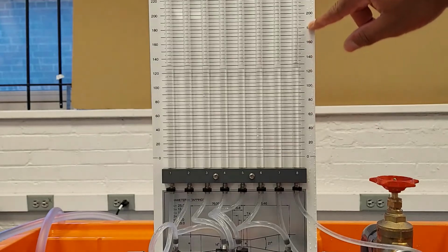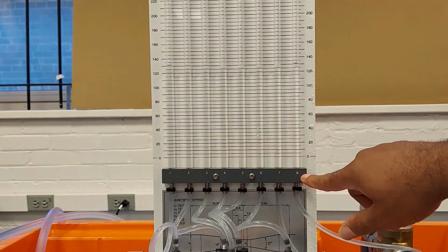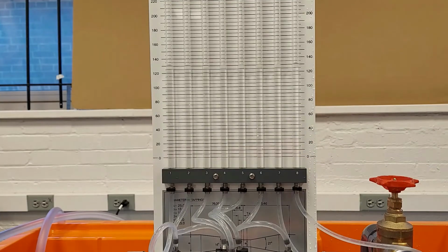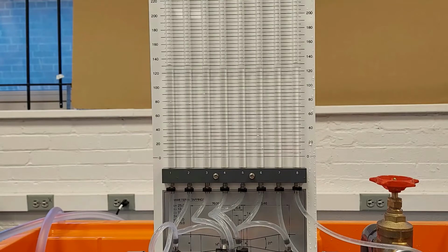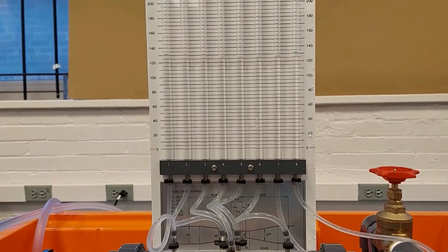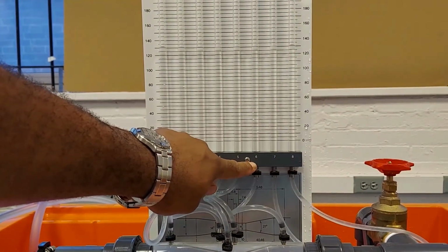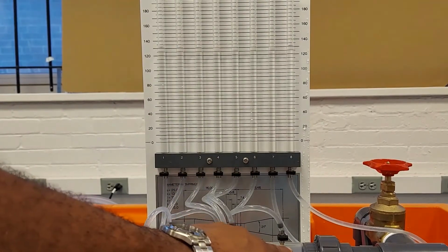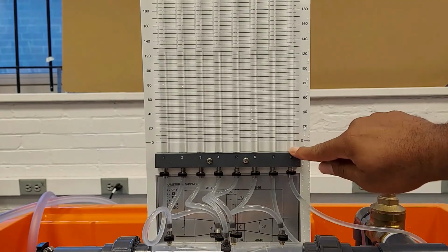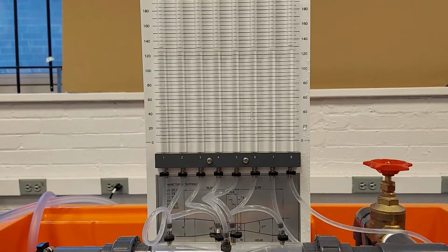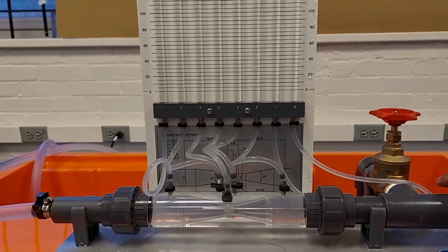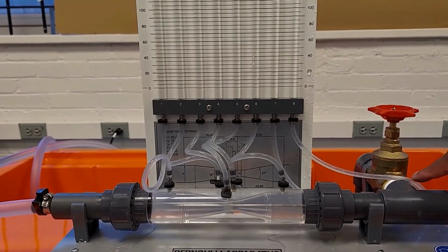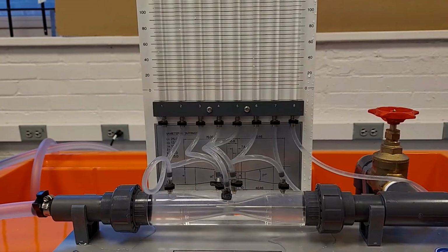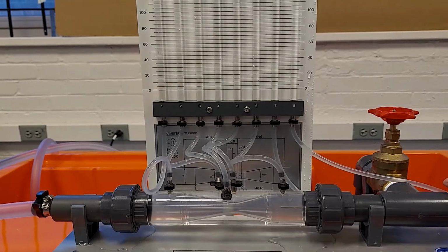The manometer readings are all in millimeters. So all our H1 to H8 readings are in millimeters. Now that the equipment is ready, what we will be doing today, we are going to be observing H1 readings from 1 to 6. That's our static pressures. And then we're going to also observe H8, which will be our total head probe, which can be adjusted. As you can see, the probe moving inside. So we would adjust the probe to each reading H1, H2, H3, H4, H5, and H6.